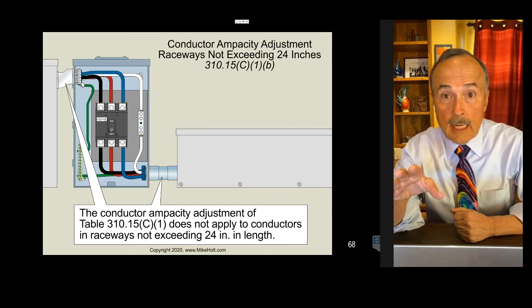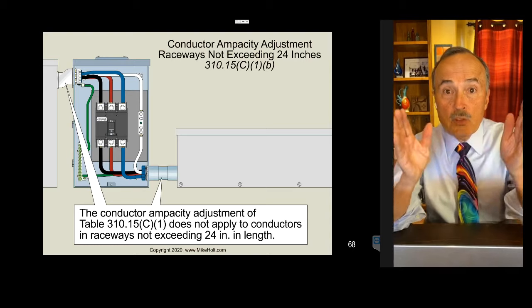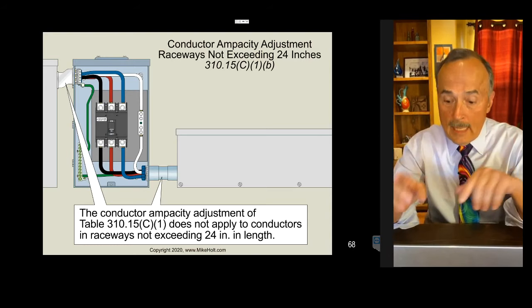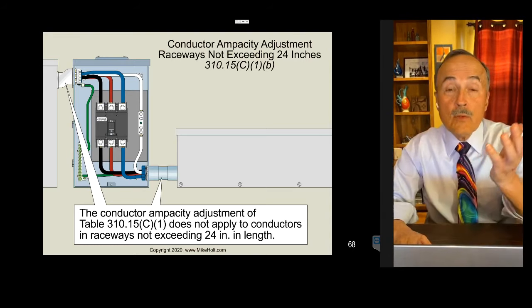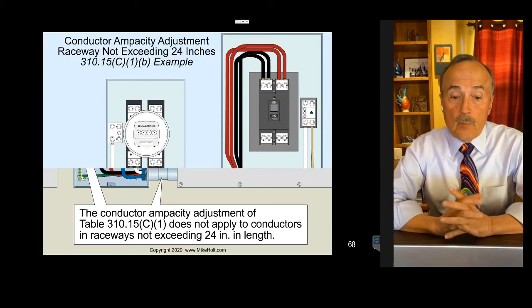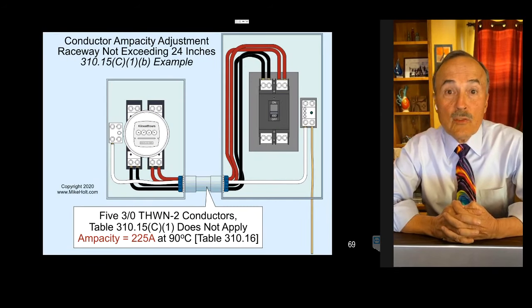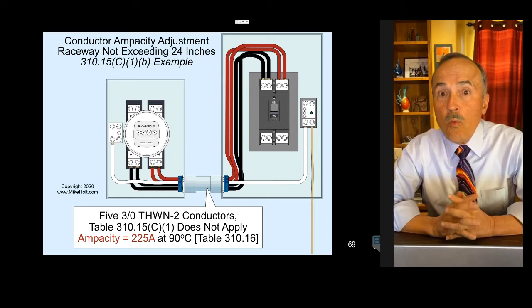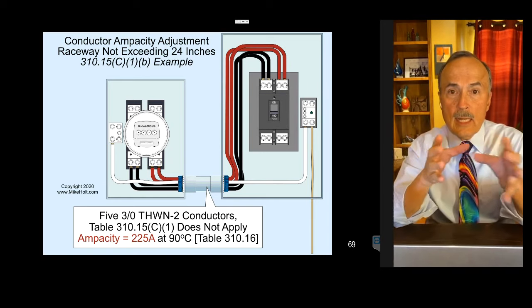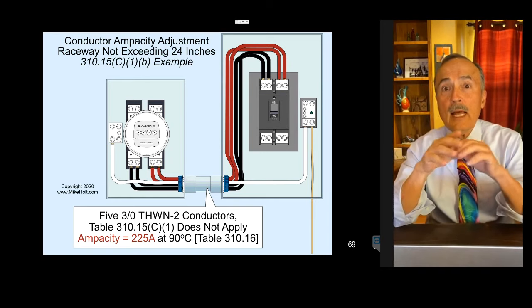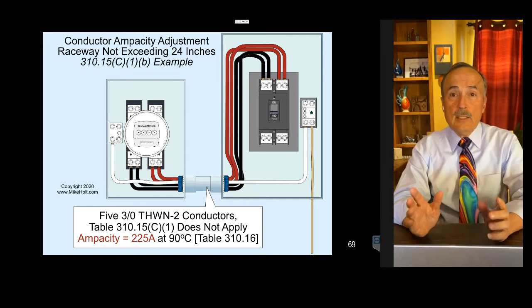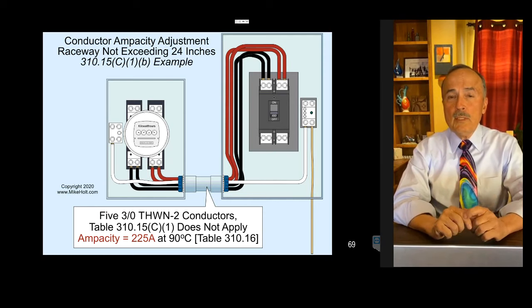But the logic is this: yeah, you have a lot of conductors in a raceway, but if it's not that long, then those conductors can act as a heat sink and take the heat out to the conductors that are outside the raceway. Listen, that's the best I got, and it doesn't really matter. If it's 24 inches or less, we don't make any ampacity adjustment. Don't have to worry about why.